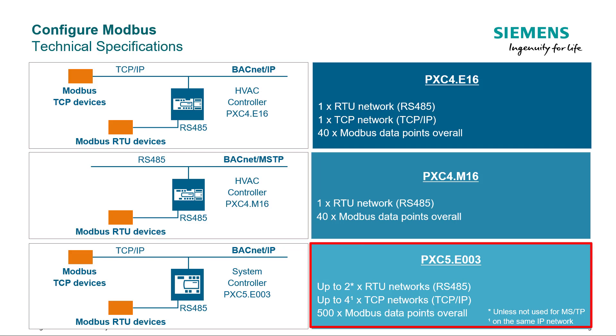PXC5: The system controller comes with larger possibilities of integrating the Modbus protocol. Since the PXC5 has two RS-485 connectors onboard, both of them can be simultaneously used for RTU networks, unless one of them is used for MSTP integration. For TCP/IP devices, it is possible to configure up to four Modbus networks under one main IP network with different ports.